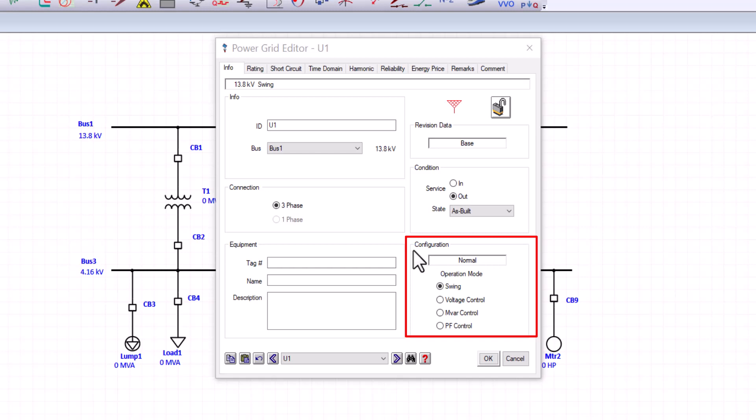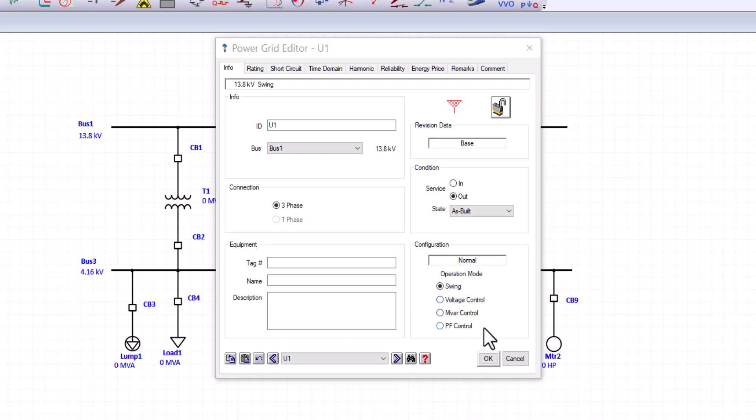This box here is the configuration box, which gives you the ability to configure your elements. This is also known as the configuration status or mode of operation. So for example, a circuit breaker can be configured to operate in the open or closed position. Loads such as motor can be operated as continuous, intermittent, or even spare. And power sources can be operated in a swing, voltage control, var control, or power factor control. But for now, you need to pick up a swing mode since this is the only power source that provides power to the system. And ETAP must have at least one source modeled as a swing to pick up the slack for solving the power flow equations.